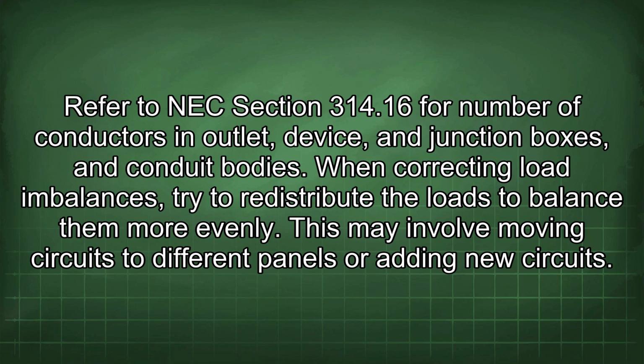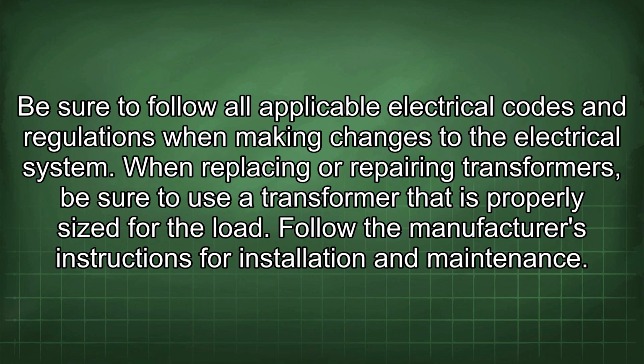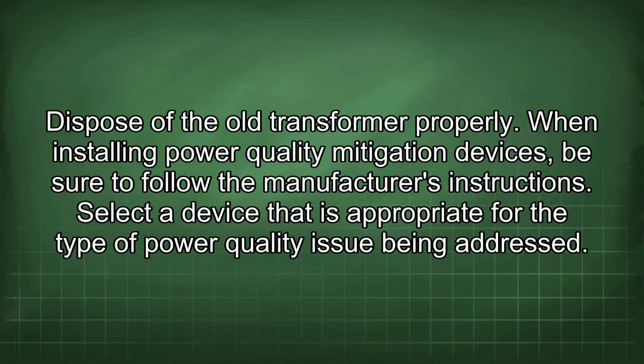When correcting load imbalances, try to redistribute the loads to balance them more evenly. This may involve moving circuits to different panels or adding new circuits. Be sure to follow all applicable electrical codes and regulations when making changes to the electrical system. When replacing or repairing transformers, be sure to use a transformer that is properly sized for the load. Follow the manufacturer's instructions for installation and maintenance. Dispose of the old transformer properly.